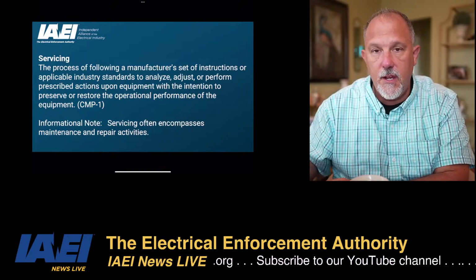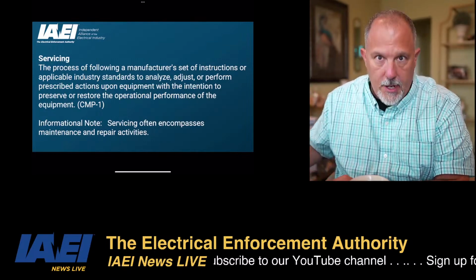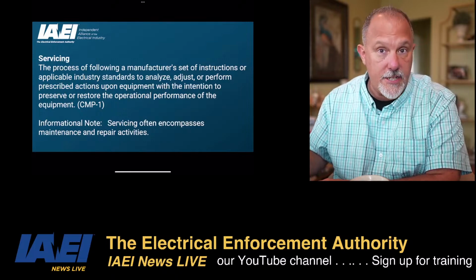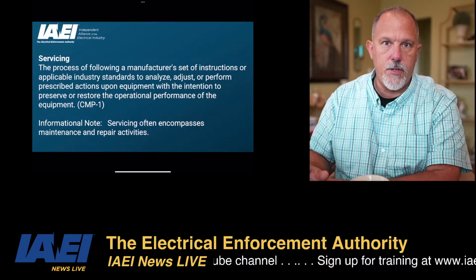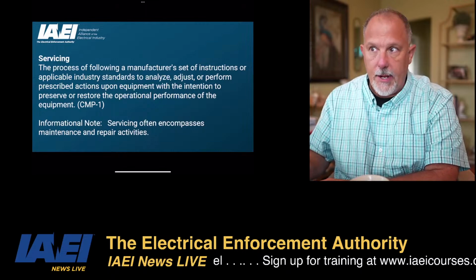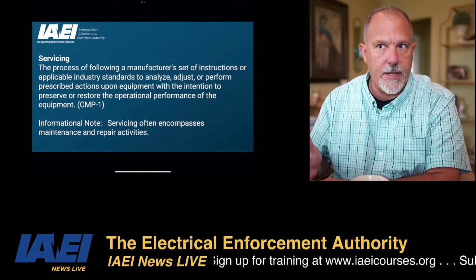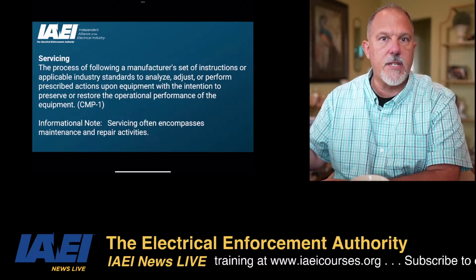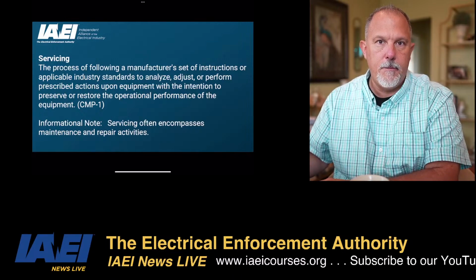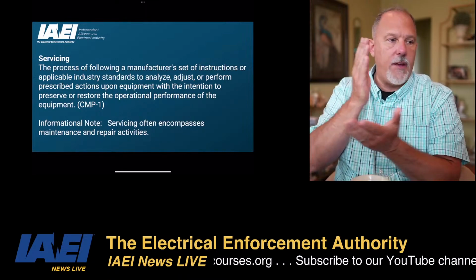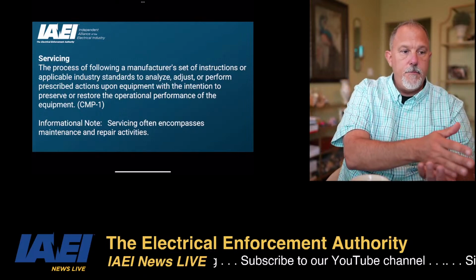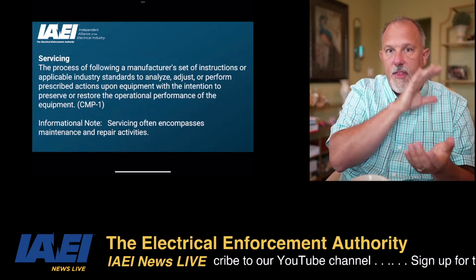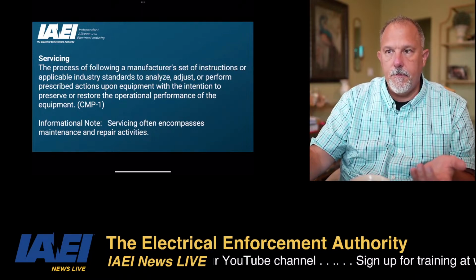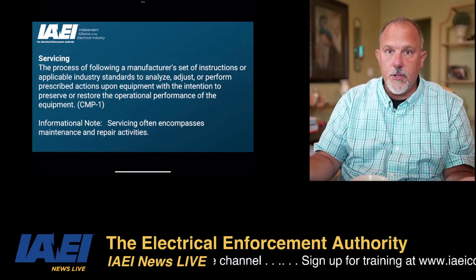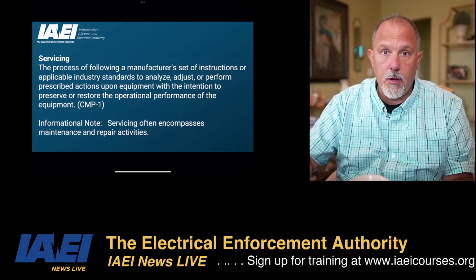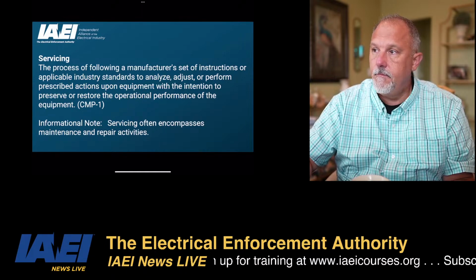So for the public input phase of the 2026 code, I went through every place where we said repair and entered the correct word, whether reconditioning or servicing. I believe everywhere I found it, it was servicing, not reconditioning. But if you just say repair, it's vague—I could say I'm repairing it, really reconditioning it, and claim it's permitted because it says I shall repair it. If instead we say it's really servicing, because you have to follow the manufacturer's instructions or applicable industry standards to bring it back to operational performance, that's servicing. If you go outside what the manufacturer allows for their product, now you're reconditioning it. Very good distinction.